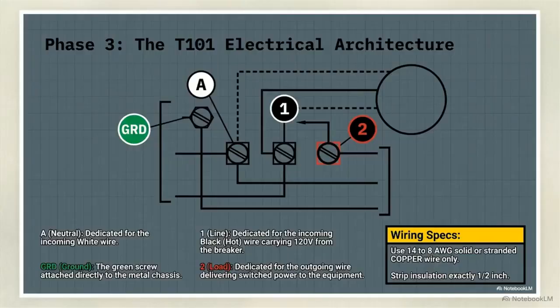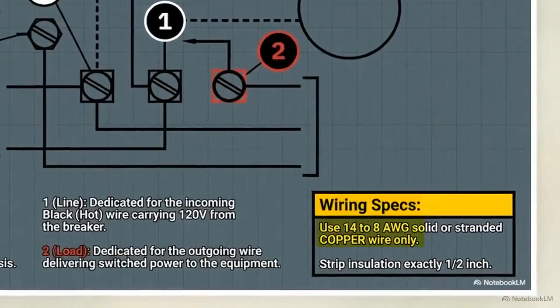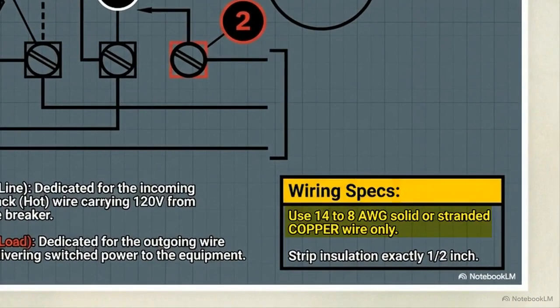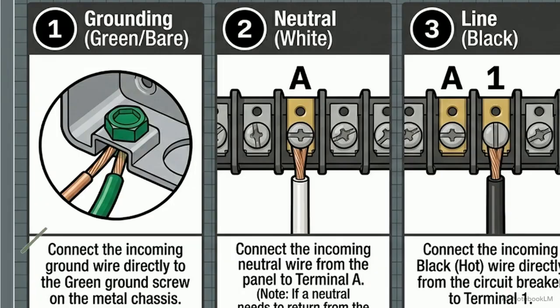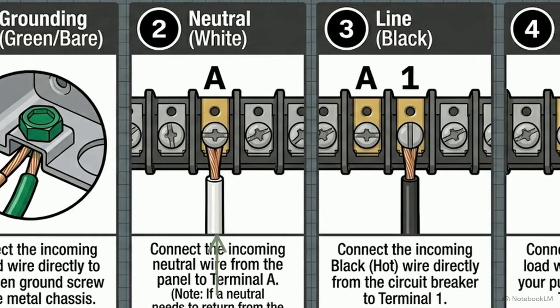This schematic details the T101's electrical architecture. Notice the specific wire requirements. You must use 14 to 8 AWG solid or stranded copper wire only, and strip exactly 1/2 inch of insulation for your connections. Step 1. Connect your bare or green incoming ground wire directly to the green ground screw attached to the metal chassis. Step 2. Route the incoming white neutral wire from your breaker panel and secure it under the brass screw at terminal A.